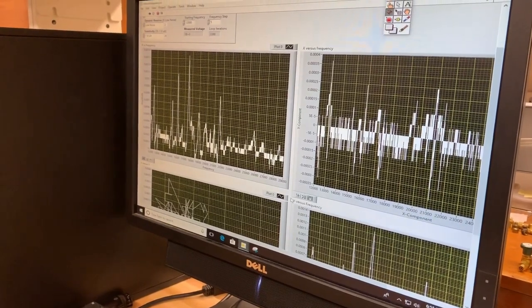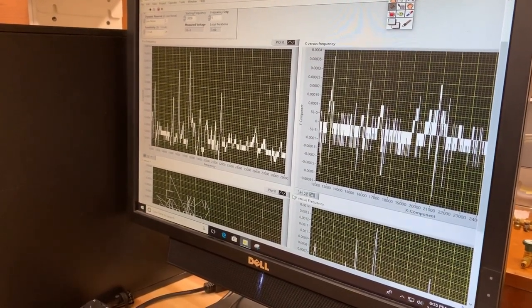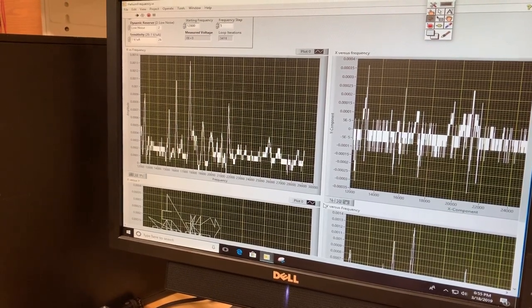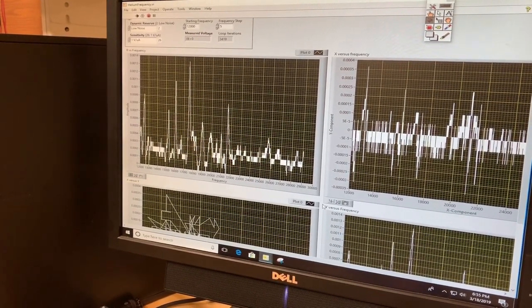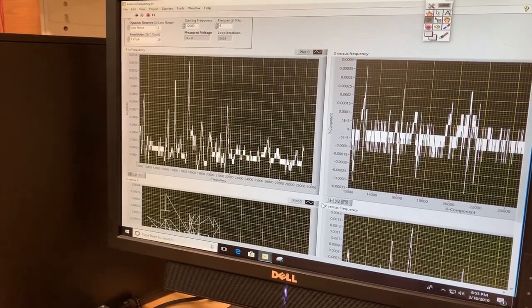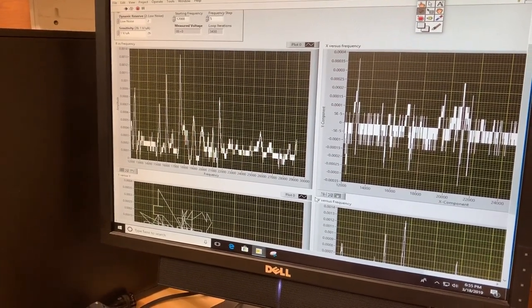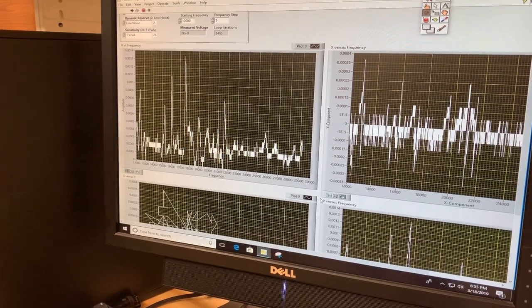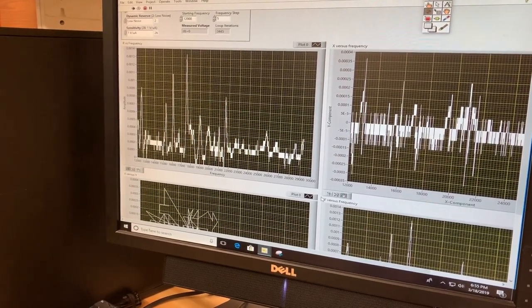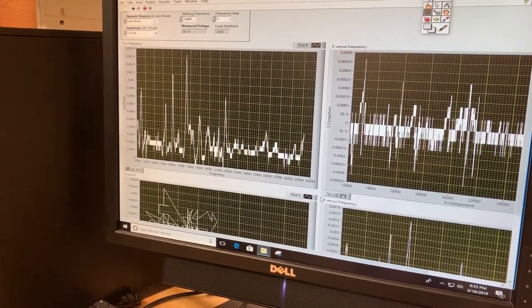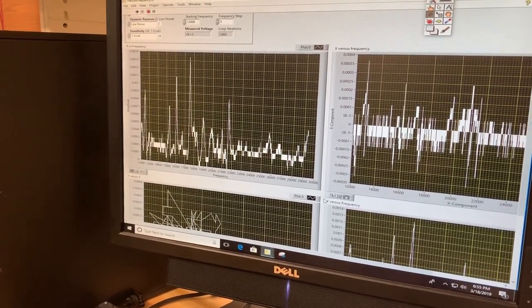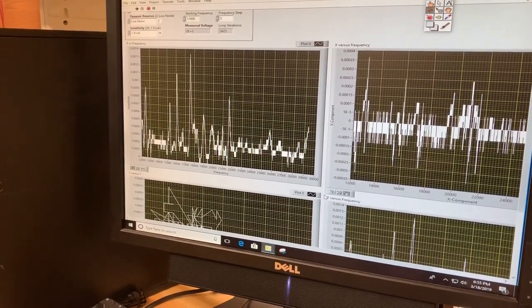Okay, so clearly it's just noise. Of course, there's going to be some spikes, but they're very short compared to any resonance as we saw, and they're absolutely not in the same places. They're random and small noise, so the fact that we've got only noise over the range that covers the two biggest spikes means that, in fact, they were air resonances and not vibrating pieces of metal or pieces of equipment. So that's a good result.